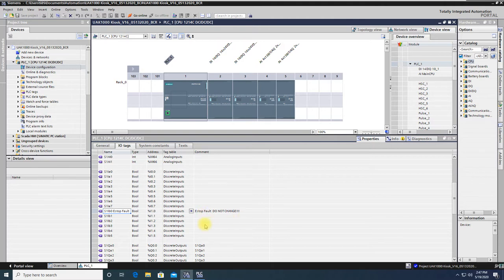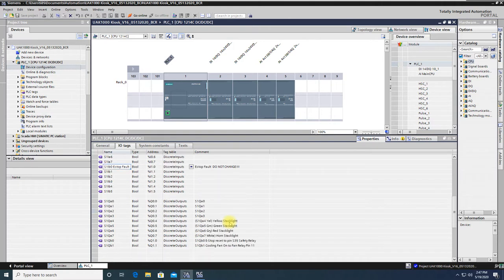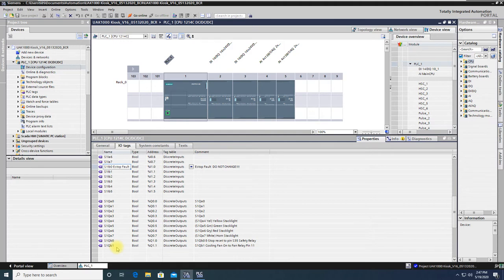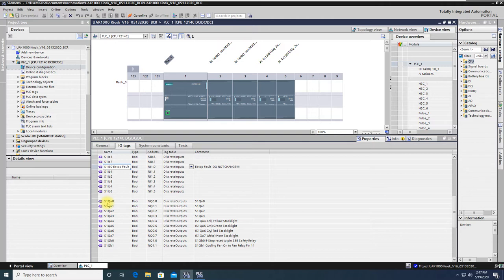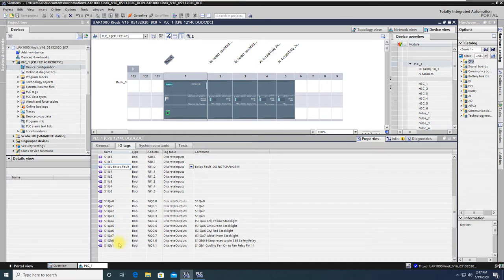Also, on the main CPU, are discrete outputs. There is a number of them, 10 of them in this fashion. So we have 8 in a group A outputs, and then a B group. So it will be designated as slot 1, this PLC CPU there. Q is Siemens' acronym for outputs, group A, with bits 0 to 7, and group B, which in this case, because of only 10 outputs, has 0 and 1.